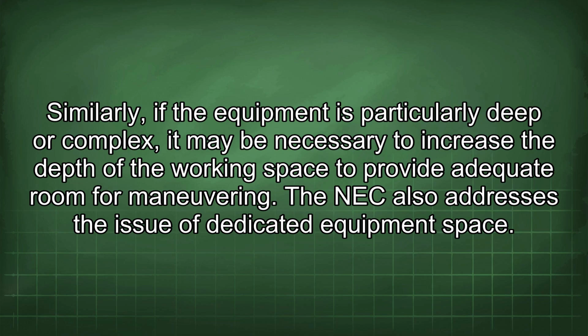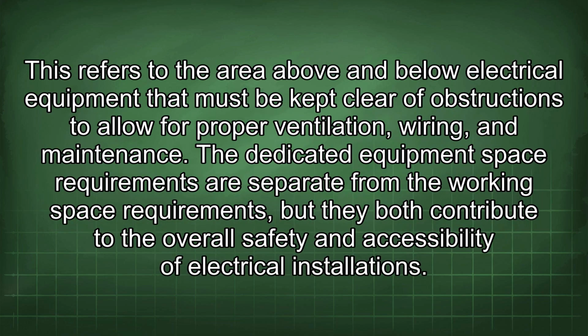The NEC also addresses the issue of dedicated equipment space. This refers to the area above and below electrical equipment that must be kept clear of obstructions to allow for proper ventilation, wiring, and maintenance. The dedicated equipment space requirements are separate from the working space requirements, but they both contribute to the overall safety and accessibility of electrical installations.